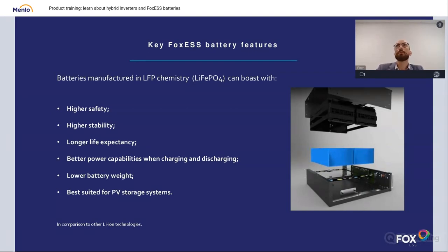So about the weight, you may be expecting less, but that second person on site will come in handy. This chemistry is best suited for PV systems because we can input and output energy from that cell without it getting warm. It's very low internal resistance. So when you charge or discharge those batteries, they are not getting warm. I've tried 4 full nominal power charge and discharge cycles and checked the chassis temperature. It was about 32 to 34 degrees Celsius.